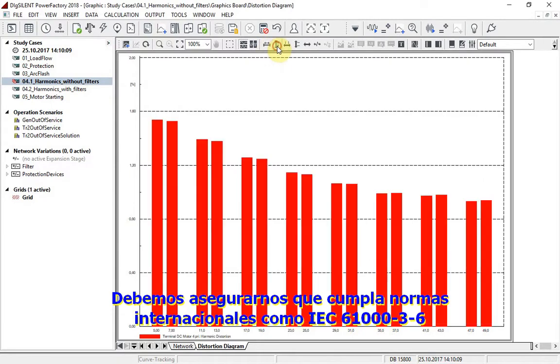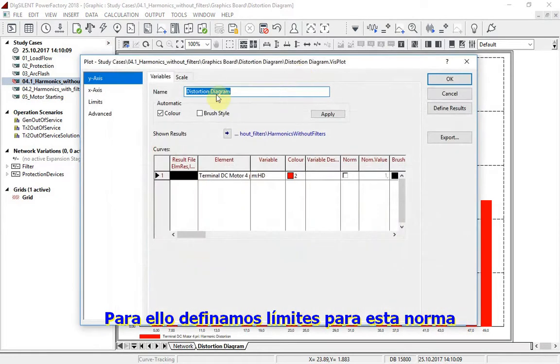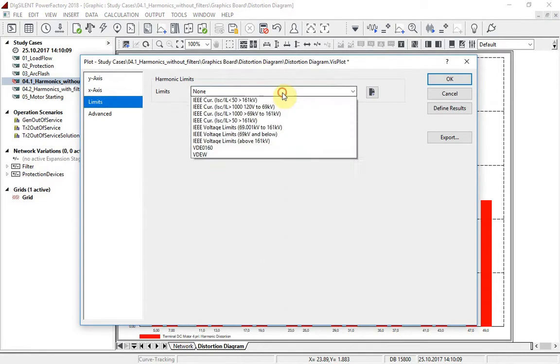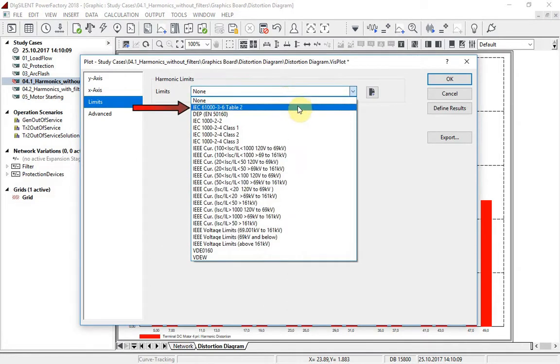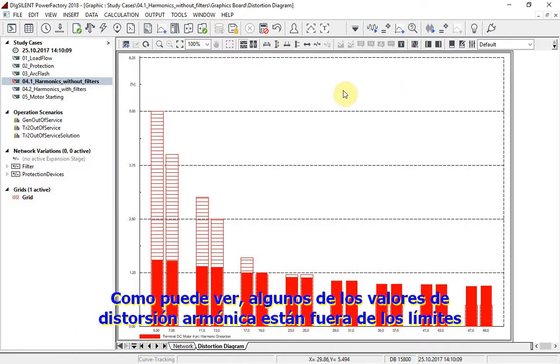We have to ensure compliance against international standards such as IEC 61000-3-6. For this, let us add limits defined in this standard. As you can see, some of the harmonic distortion values are out of the defined limitation.